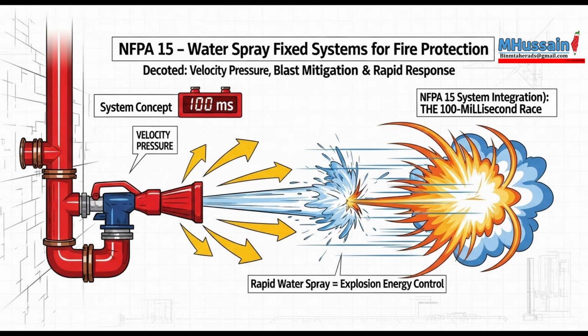Okay, direct interaction. But for non-water soluble materials, think gasoline, propane, natural gas, you can't absorb it. The water doesn't mix. So here, the water spray has to rely purely on dispersion. Like using the spray as a big fan. Essentially, yes. The high-velocity spray pattern acts as a massive mechanical air mover. It creates turbulence, stirs up air currents, and physically mixes the vapor cloud with fresh air to dilute it below the LFL. So for those non-soluble cases, the spray density and pressure calculations aren't about cooling, they're about generating enough air movement. That's a different kind of fluid dynamics problem.